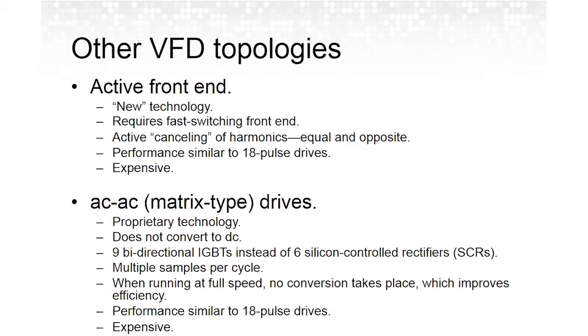The first one is an active front end. Again, this isn't a new technology. With the active front end, our biggest concern is the harmonic distortion that we're introducing by the input of the VFD back onto the source and messing up other things that are connected to that same source with dirty power. What the active front end does works similar to the concept of noise canceling headphones. We're basically inserting equal and opposite amplitude back into the input to cancel out the harmonics that we're creating.